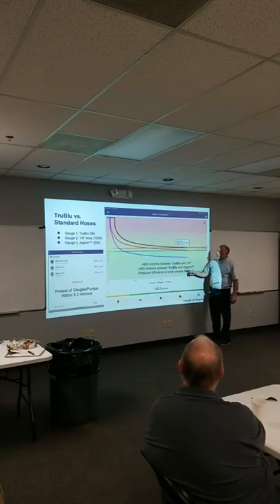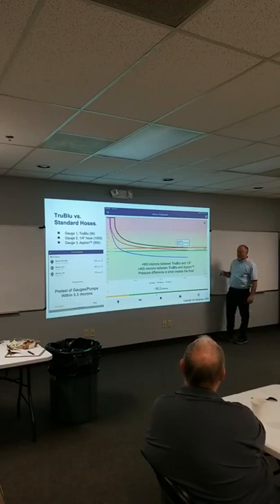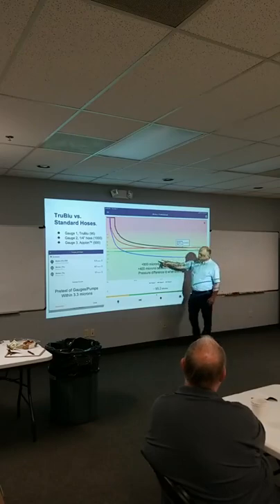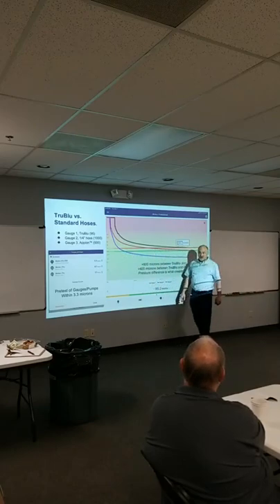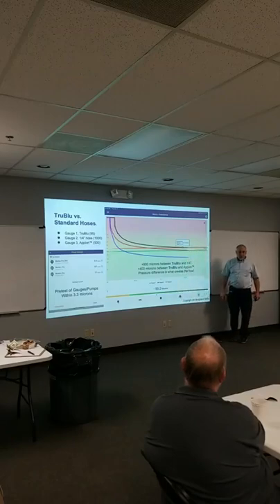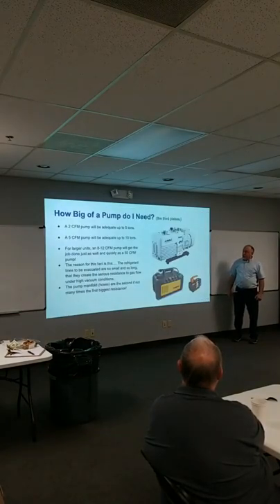I gave up on this 1/4 inch hose because at 14 minutes I hit 1,000 microns, and you can see it's sort of flattening out. It's going to be way out here sometime at maybe half an hour to get the same thing. So literally 30 minutes for the 1/4 inch hose versus about 2 to 3 minutes, 2.5 minutes to the same thing with a TruBlu hose. Literally just increasing the hose size, right? Same 3 pumps, different hoses on there, difference is the flow.